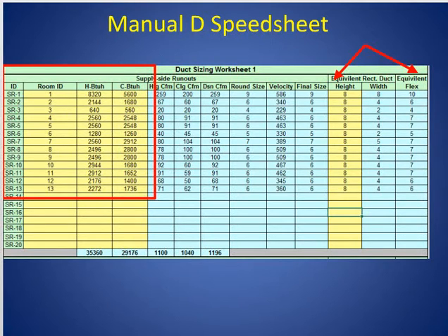For balancing, you've got to pick the heating or the cooling, and in this case, it looks to me like you can easily get within 15% of design and meet the quality installation requirements of 20% by balancing the system, and you can put it between the values. For instance, if you look at SR8, you have 78 and 100. So you can get within 20% of both of those by putting it in the middle. If you had 90, you'd be in the middle, and you'd be within 20%, and you'd meet the QI requirement. Or if you decided that it needed more cooling, you could just balance it to the 100 for the cooling.